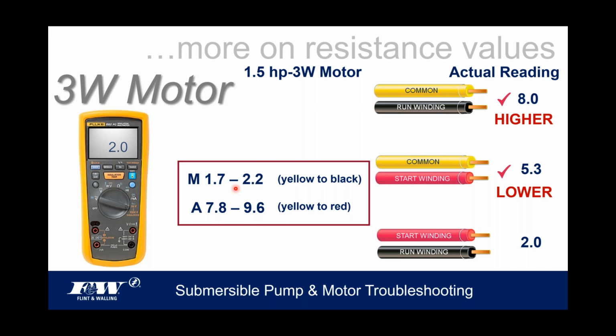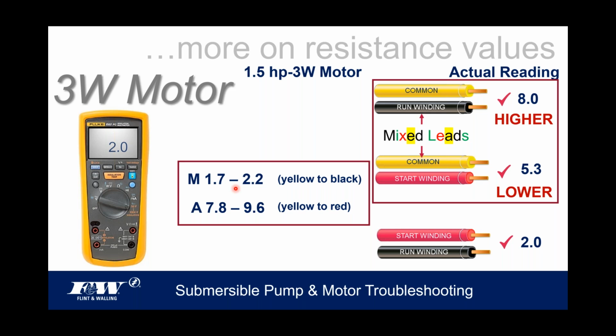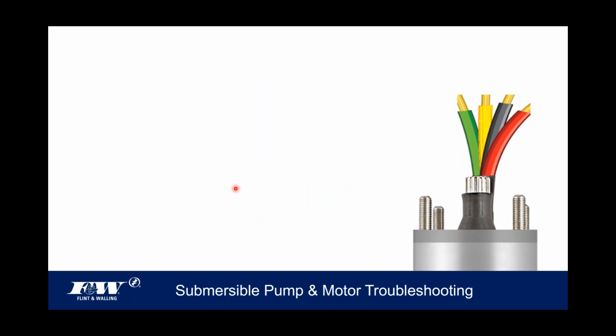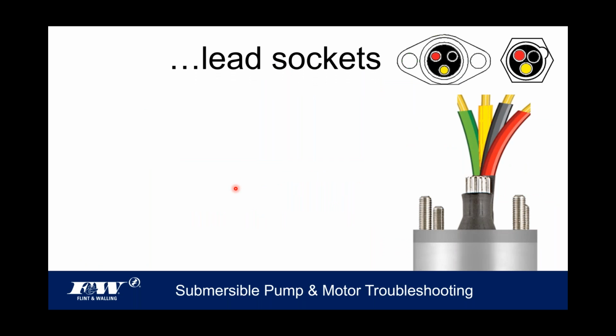And the problem here is that anytime you have readings that are coming in both higher and lower, that is an indication of what is called mixed leads, all right? And again, this is not a very common occurrence. It's the rarest of all of them, but it happens. You ask, okay, well, what are you talking about, mixed leads? I suppose that when the manufacturer puts the lead socket in the motor and they wire the bottom side of that, if they didn't wire that properly, and now you put your motor lead down on top of that, you're not lined up. Your red wire's not lined up to the internal red or the internal yellow. They're off one. Who knows?